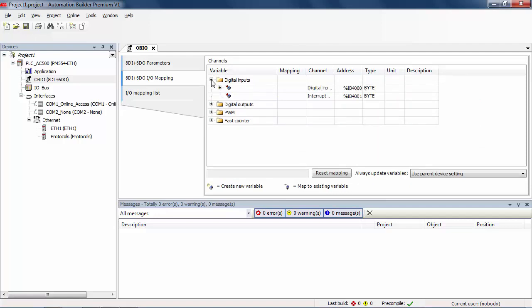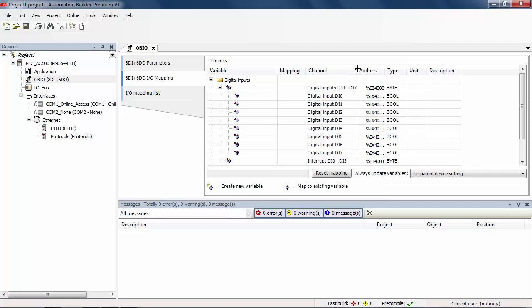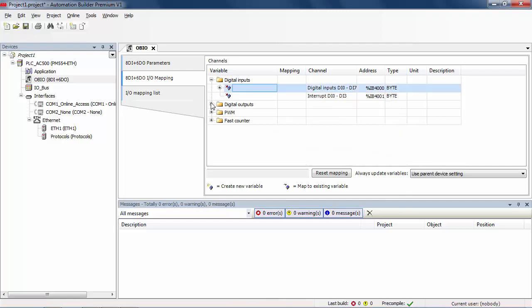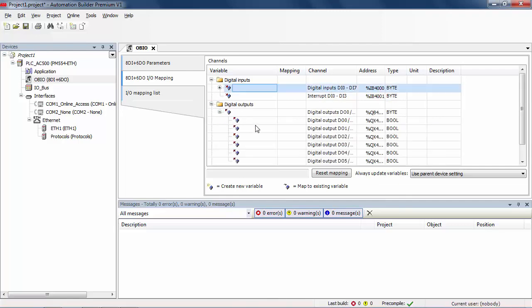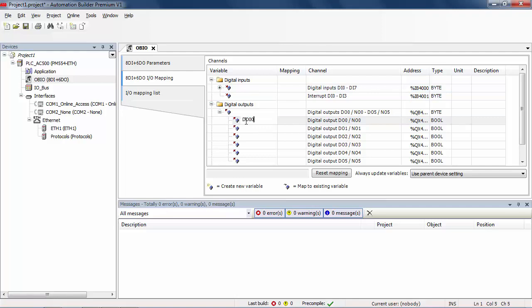All available IO channels get automatically an IO address, and then the symbolic names and descriptions could be defined. In our example, just some IOs have been declared for an easy and fast configuration, but of course more IOs could be added later in the project according to real application. After creating the configuration data, the IO channels with symbolic names will be automatically added to the global variable list in IEC 61131 application.